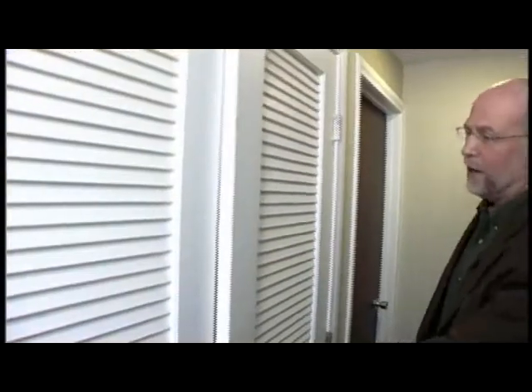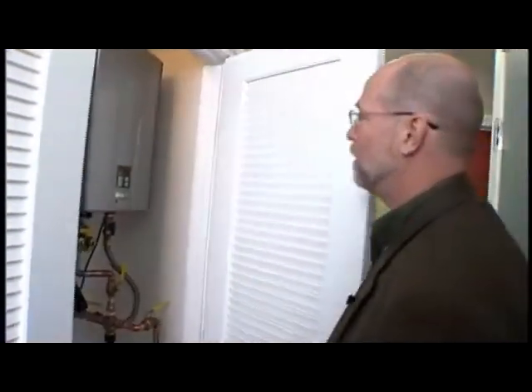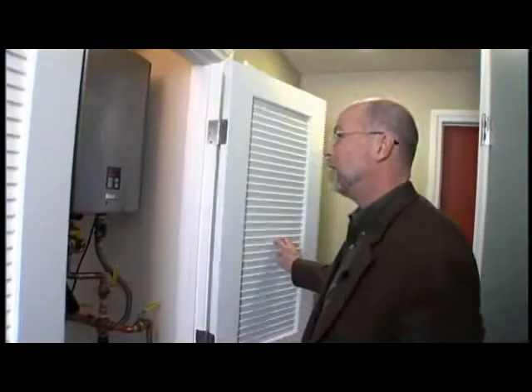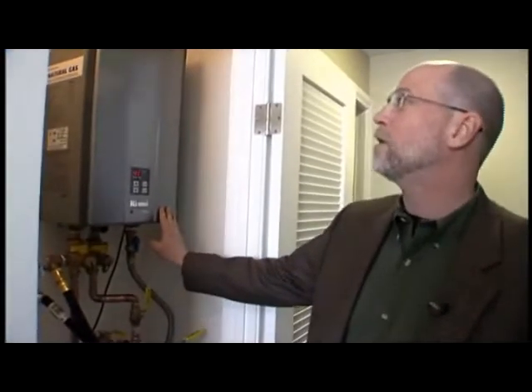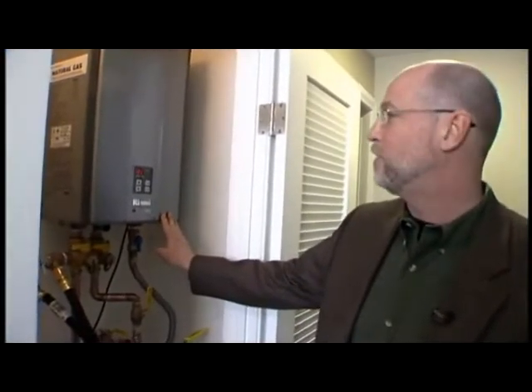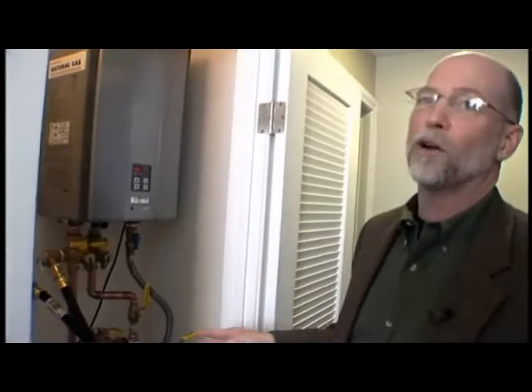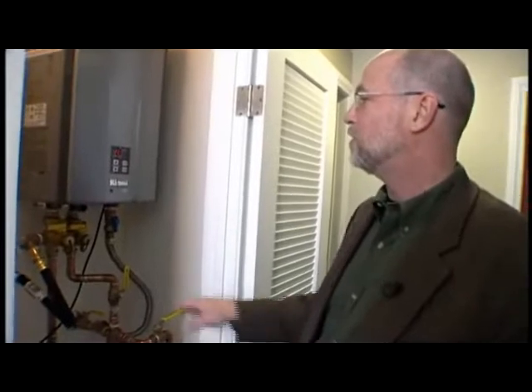When doing an energy efficient house, the heating and cooling loads are usually the highest energy uses. But when you have a very efficient house, like we do here, it's the domestic hot water that ends up being the highest use. So we've got to come up with a strategy that equals the energy efficiency of the heating and cooling for our domestic hot water. And what we did here was a two-part strategy, starting with a Rinnai tankless water heater.